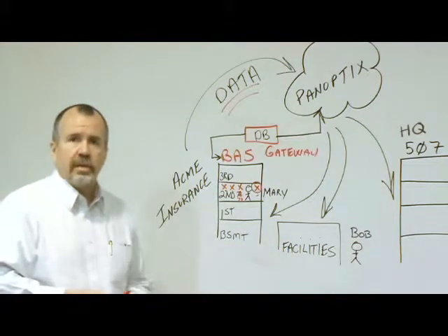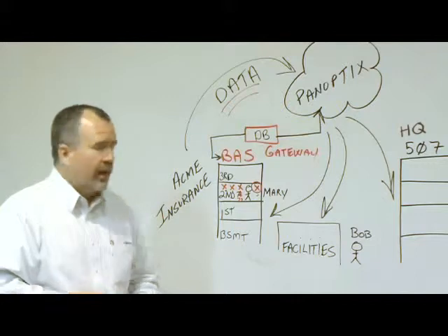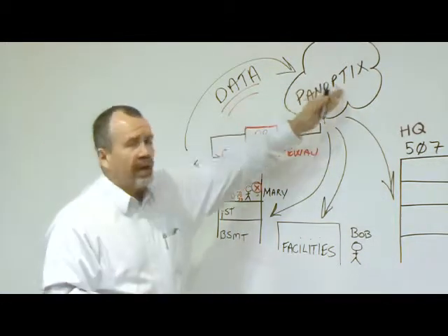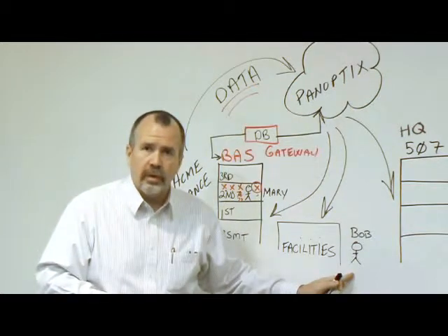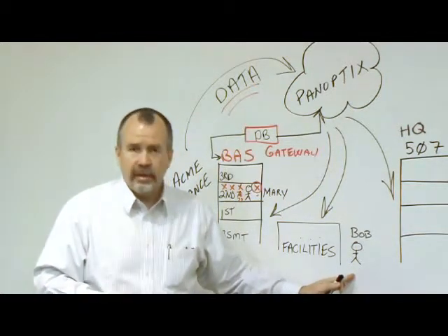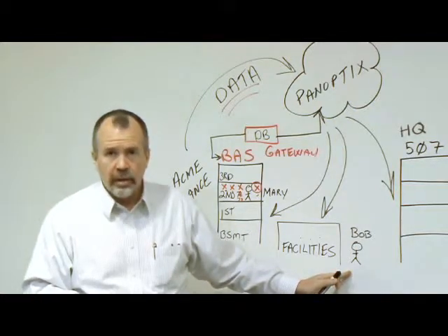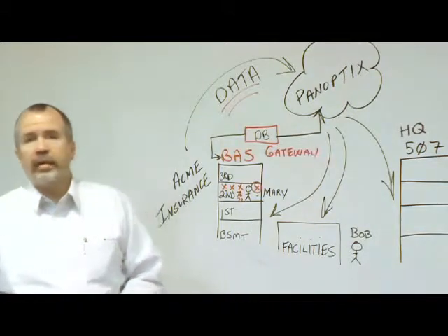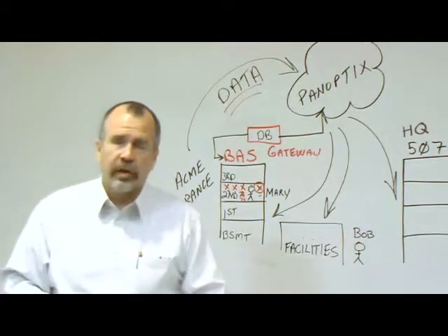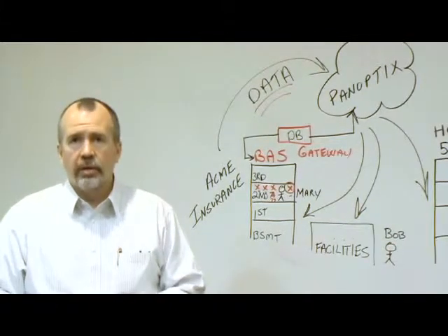And if you can make that assumption, and continuous diagnostics will make that decision for you, then the message coming from Panoptix to Bob is, don't waste your time going to the floor and popping the ceiling tile and burning some of Mary's time while she sits there and watches you do that. Go to the air handling unit and begin to help determine if we have a chill water coil problem, if we have an airflow problem, a set point, or a control problem at the air handler.